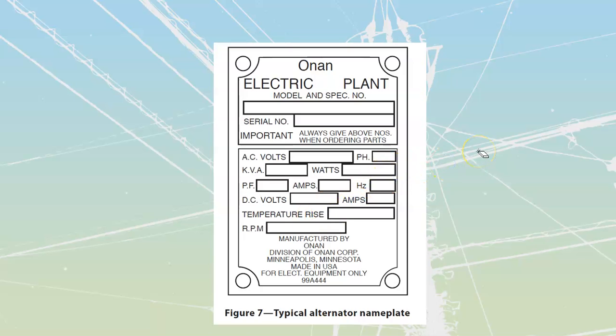Temperature rise and RPM is going to be based upon the electrical characteristics. We know for every 10 degrees over 30, we get 50% less life, so we want to keep this thing down to a relatively cool temperature so we can maintain our systems.